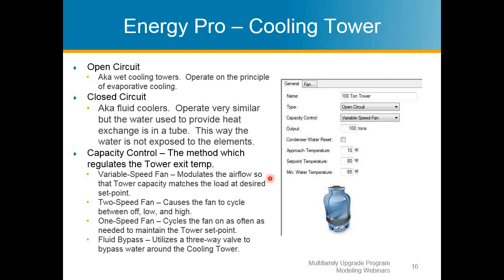Depending on where you're at and what climate you're in, you may have different approach temperatures, set point temperatures, and minimum water temperatures. You also may have different performances along with your cooling tower based on those temperatures. So it's very important to gather that information from the engineers' records that are working on the projects, to make sure you're inputting the appropriate information.